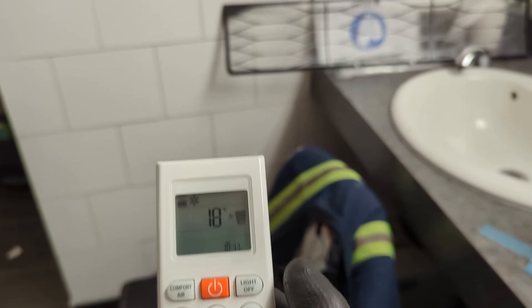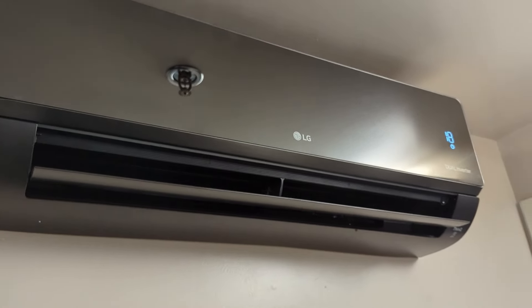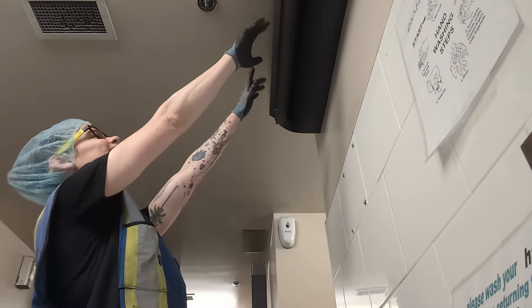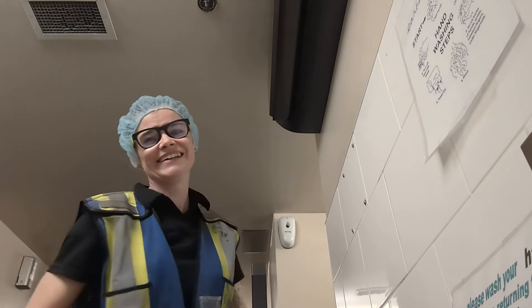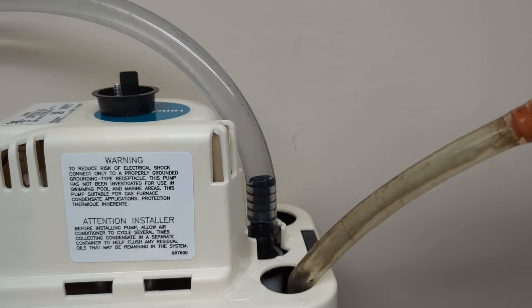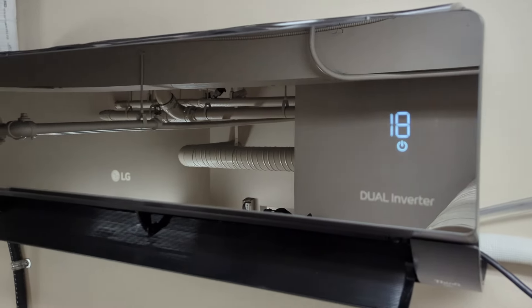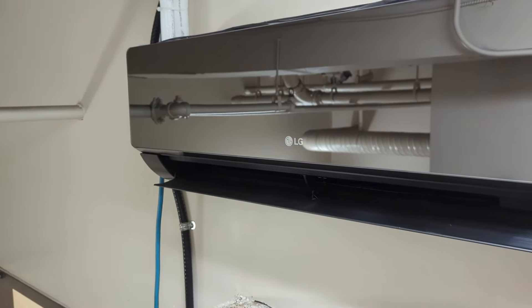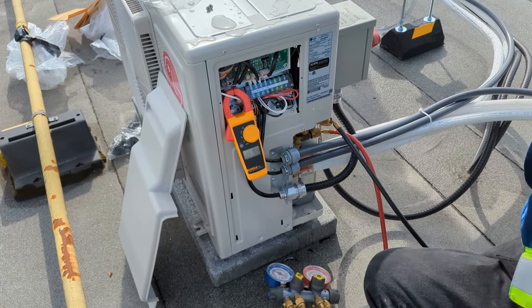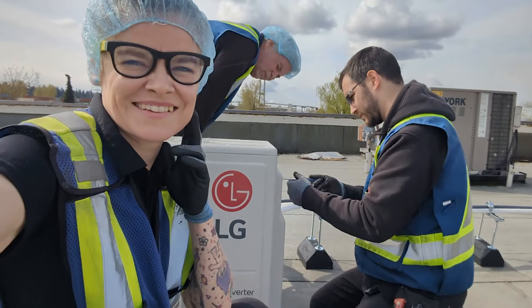And it does — it's beautiful. It pumps all the way up onto the roof. We also check the drain on the actual unit itself — we pour water down onto the coil and make sure that it pumps out. Got our little remote thermostat mounted onto the wall, and now the moment of truth. That's music to our ears. And this is one of my favorite parts — feeling that cold, cold air on me. It's so awesome. We're just testing the second condensate pump and the second drain outside of the unit. How beautiful is that mirror finish. Just making sure everything looks good on our condensing unit on the roof. And we're all dunsies.